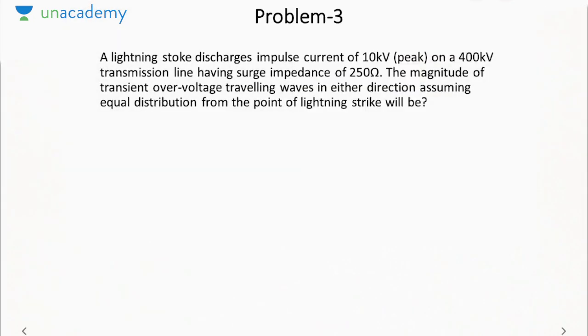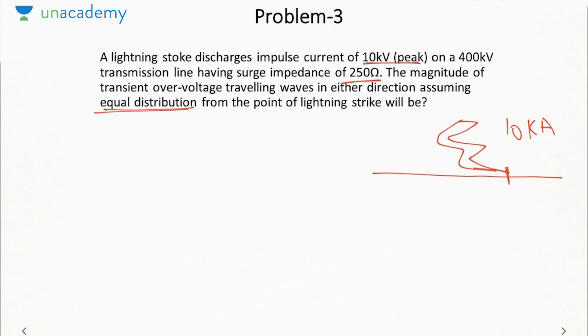In our next problem, it is saying a lightning stroke discharges impulse current of 10 kiloampere on a 400 kV transmission line having surge impedance of 250 ohm. Find the magnitude of transient overvoltage traveling wave in either direction, assuming equal distribution from the point of lightning strike. This is my transmission line. Suppose lightning is striking at this point. It is inducing a current of 10 kiloampere. Now it is saying assume equal distribution. So current will get divided 5 kiloampere and 5 kiloampere.